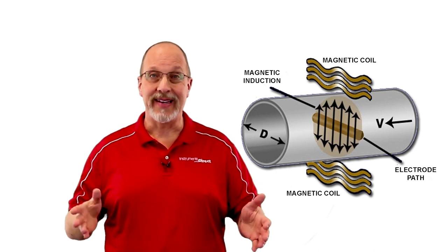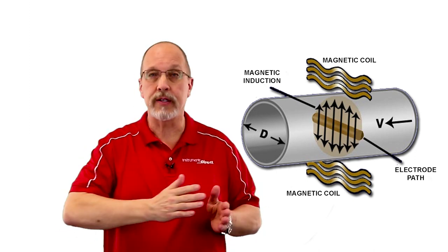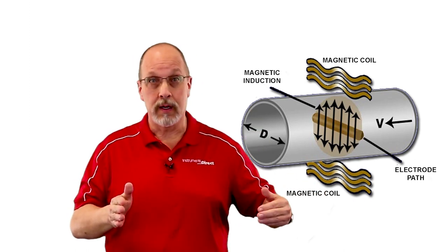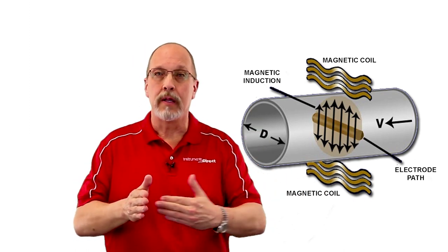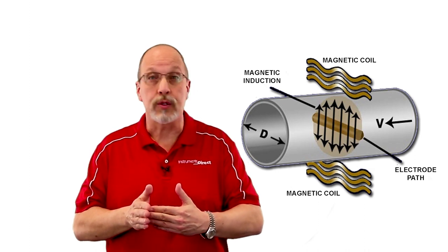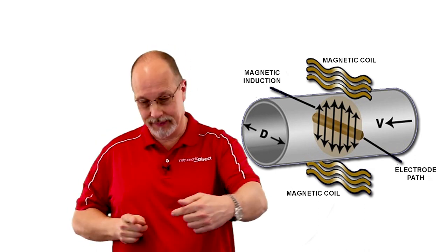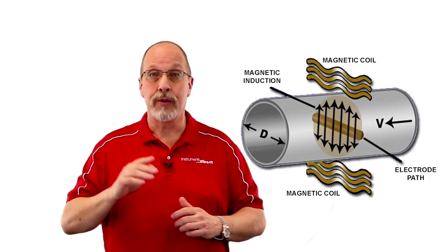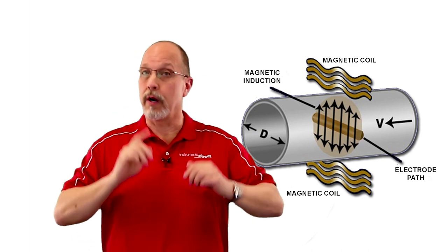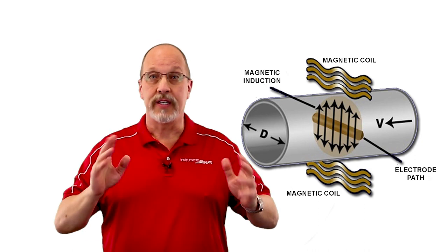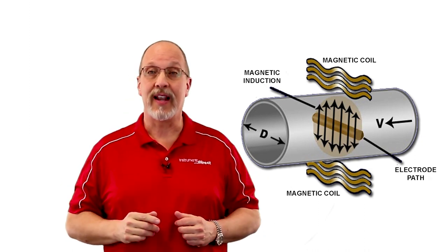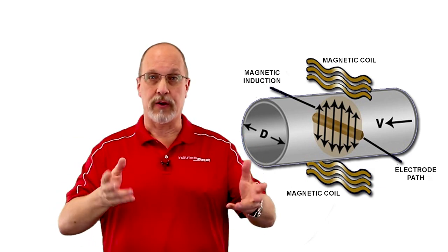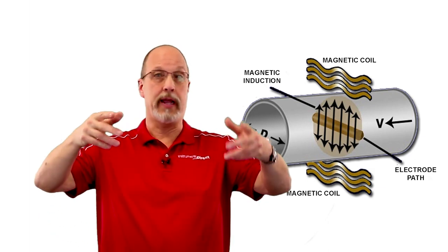Now this magnet creates a magnetic curtain across that pipe. And when the conductive liquid, water, hits this curtain at a right angle, it creates a small amount of current, which is monitored by the two electrodes. The faster the liquid flows through the magnetic curtain, the more current is generated. Since the current is proportional to the velocity of the liquid flow, we just factor in the pipe size to calculate the volumetric flow like gallons per minute.